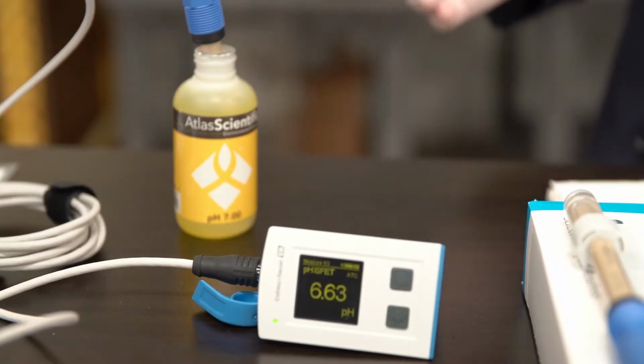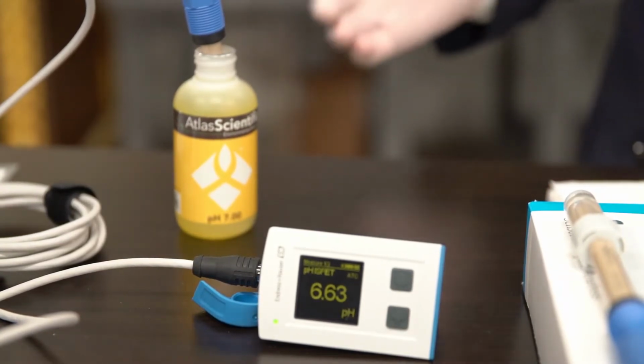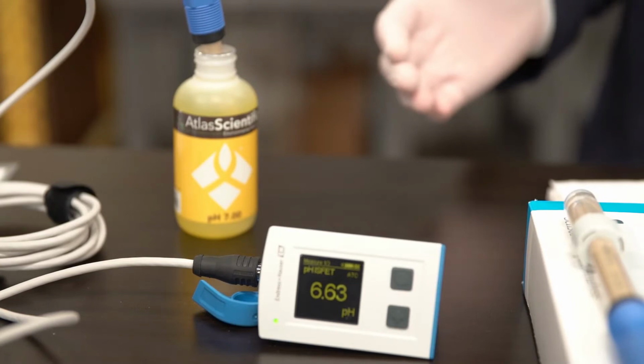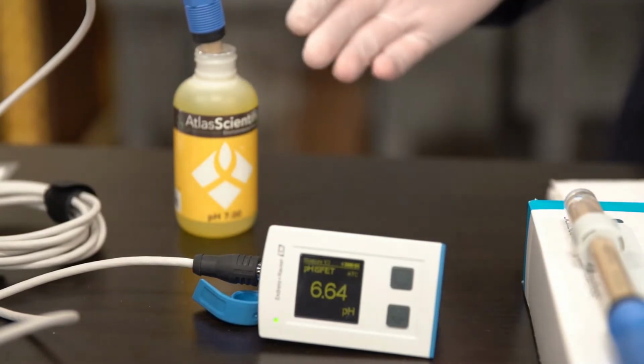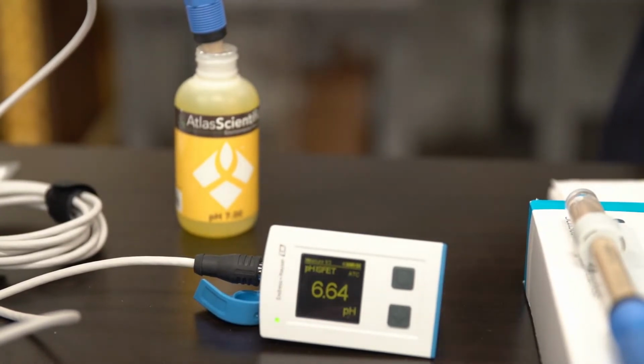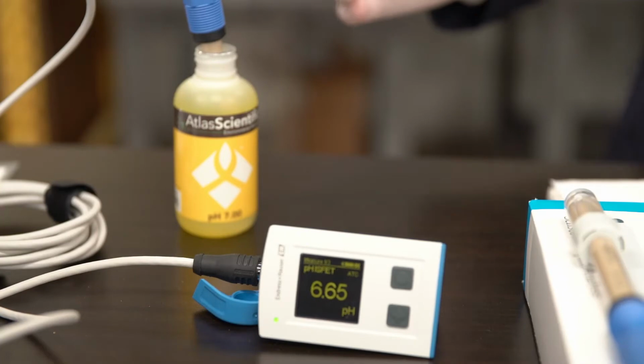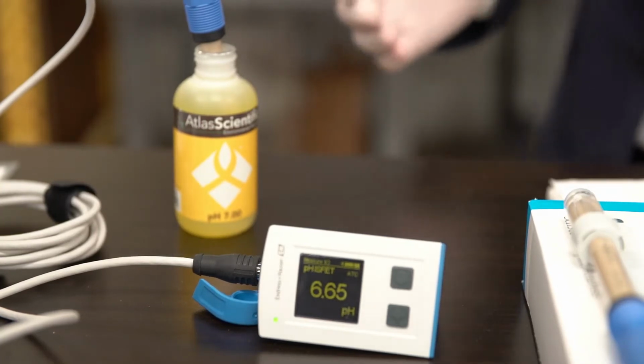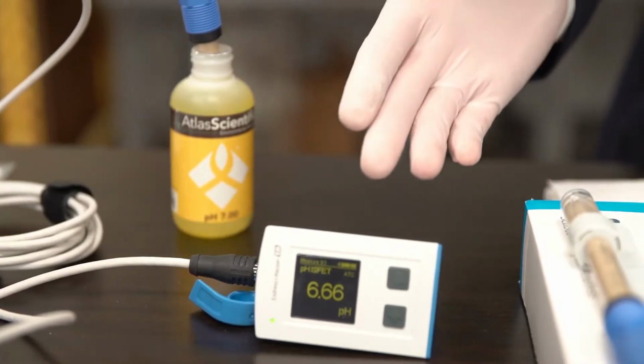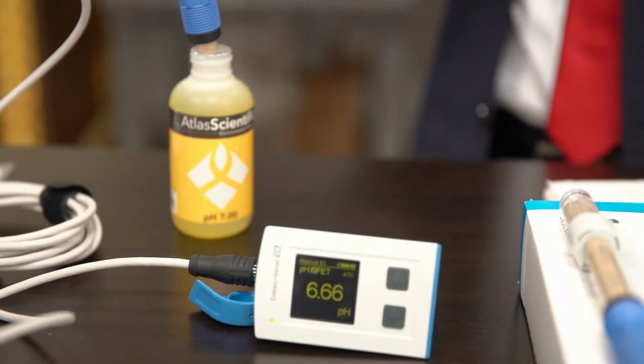So after cleaning, we check the probe reading in the pH buffers. As we see, it is out of our tolerance, which could be defined by you. But typically, we recommend staying within 0.2 pH. Now the buffer reading is 6.6. So we've got a ways to go.